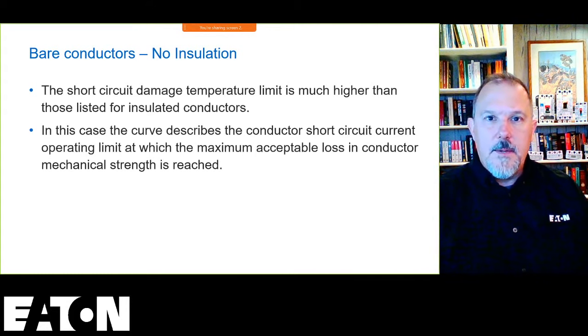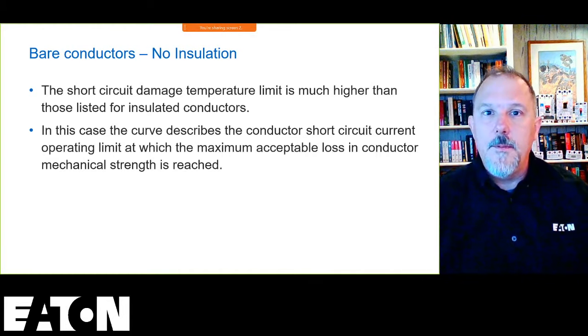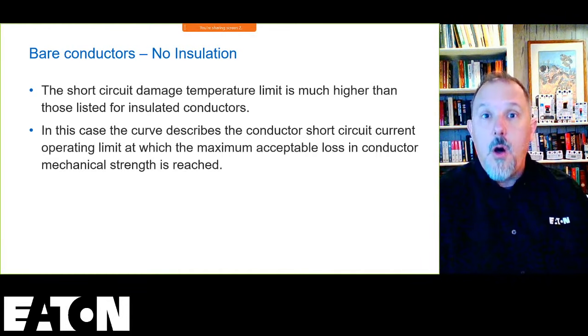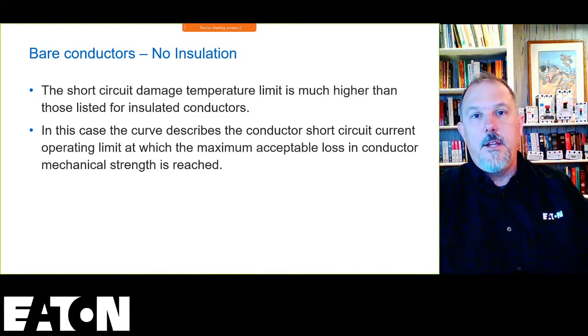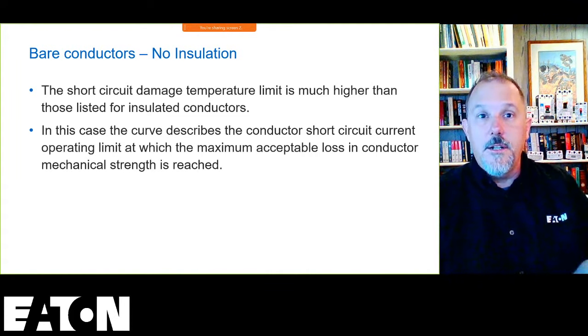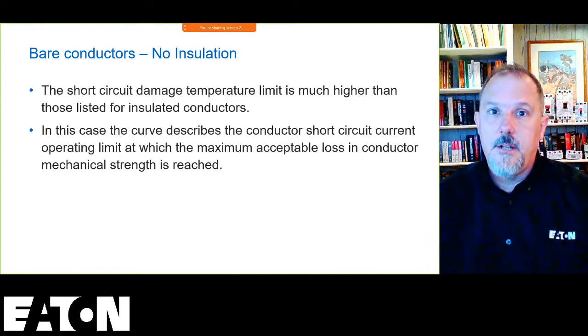We talked about a couple of those things from a copper conductor perspective, and your equipment grounding conductor. You've got to make sure that you have an effective grounding path, but you also want to protect that equipment grounding conductor. So you don't want to make it too small because ground fault currents could pass through it. And you want to make sure that your overcurrent device clears those faults fast enough so that you protect those conductors as well as your ungrounded conductors that are insulated.